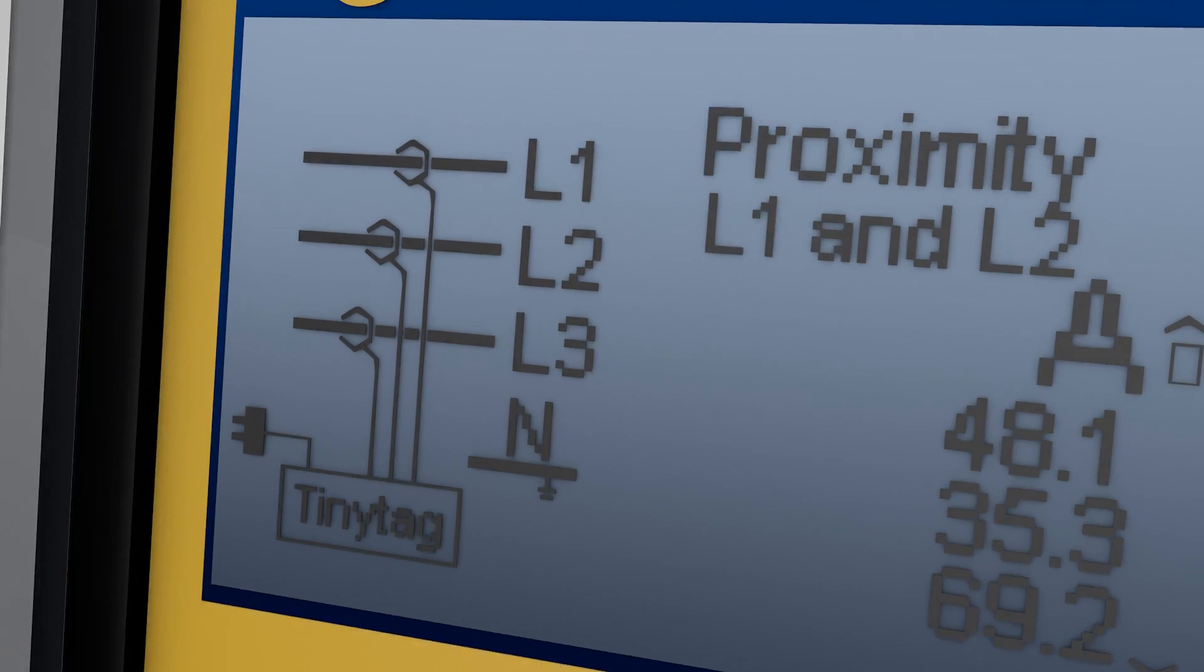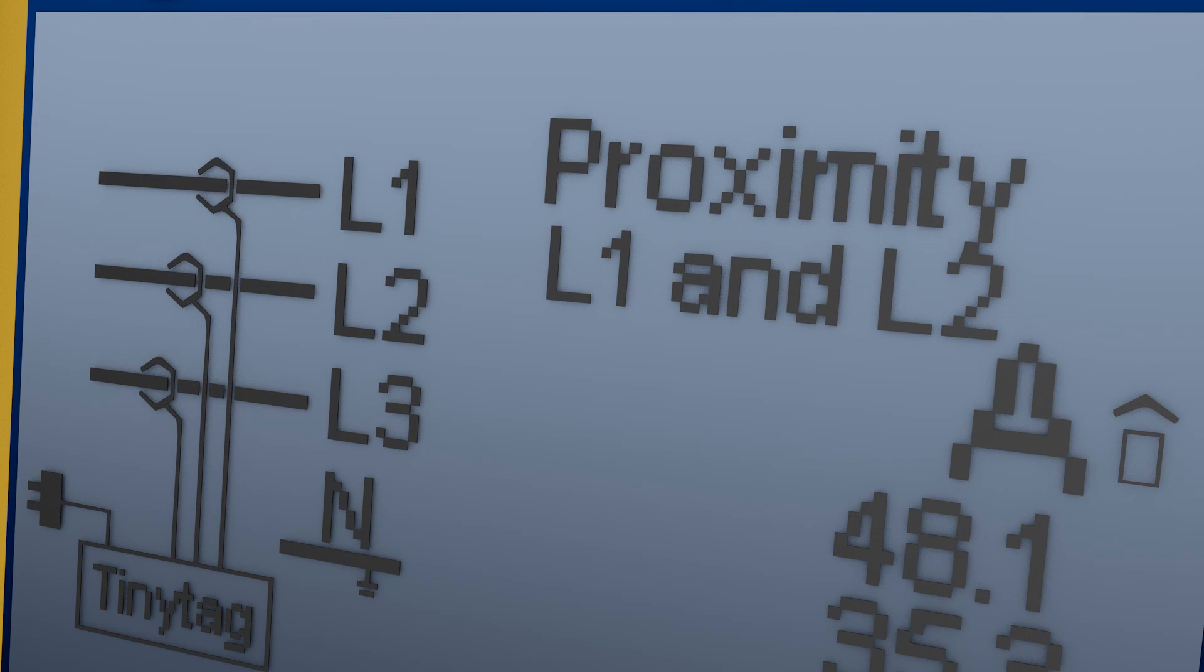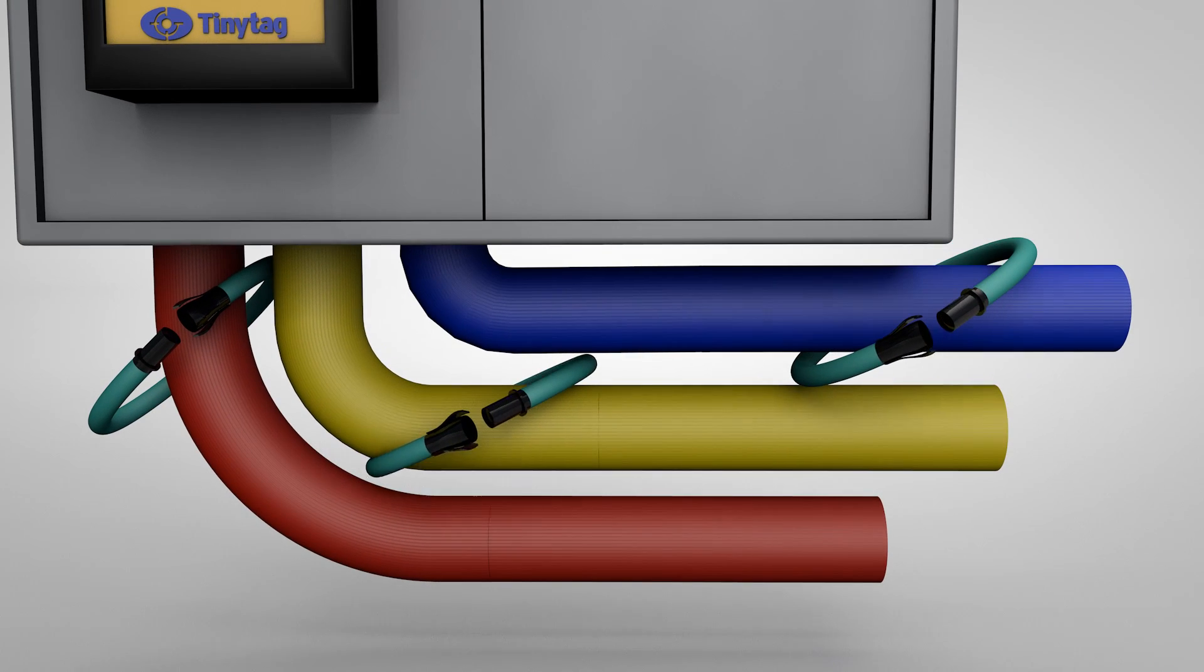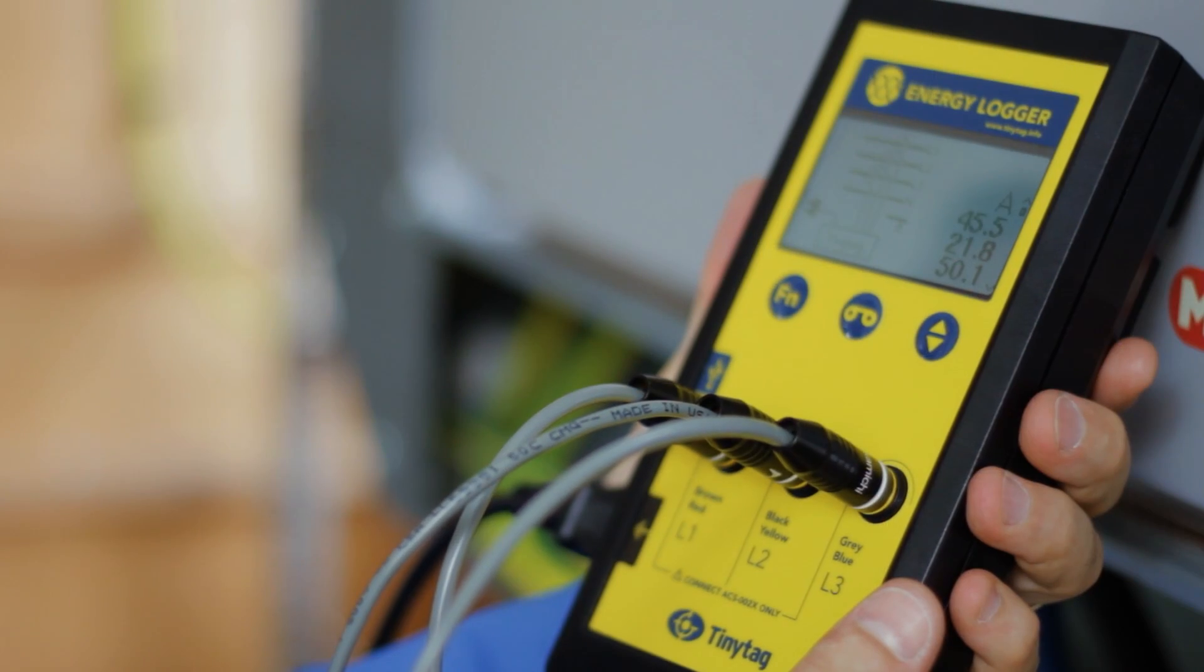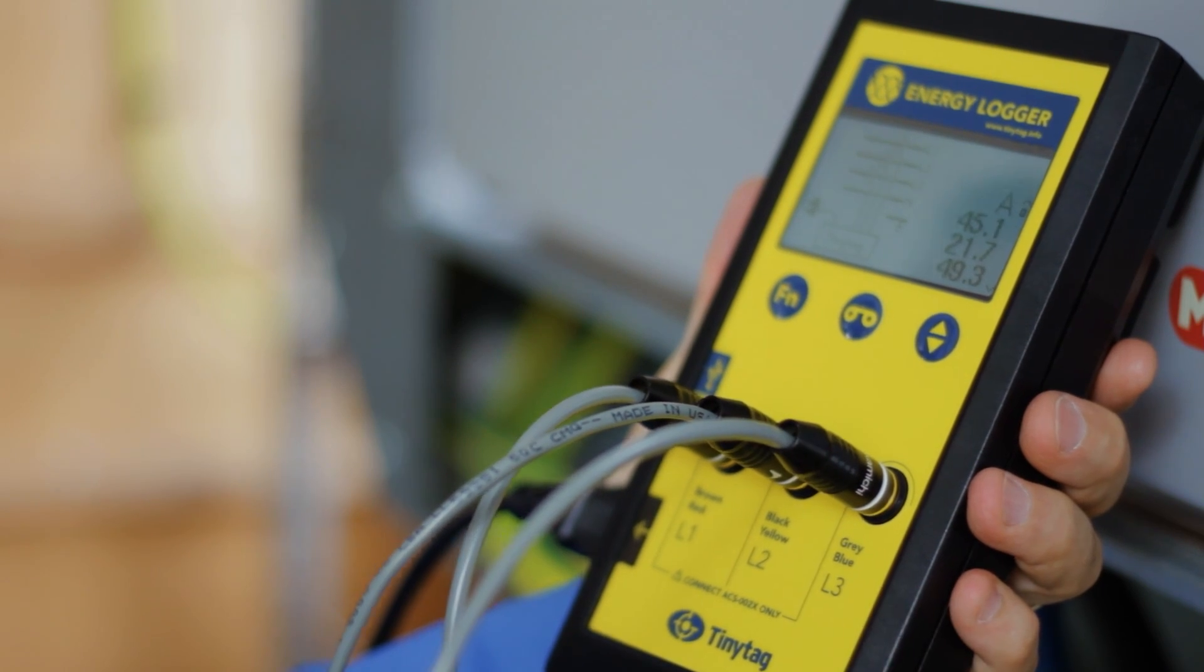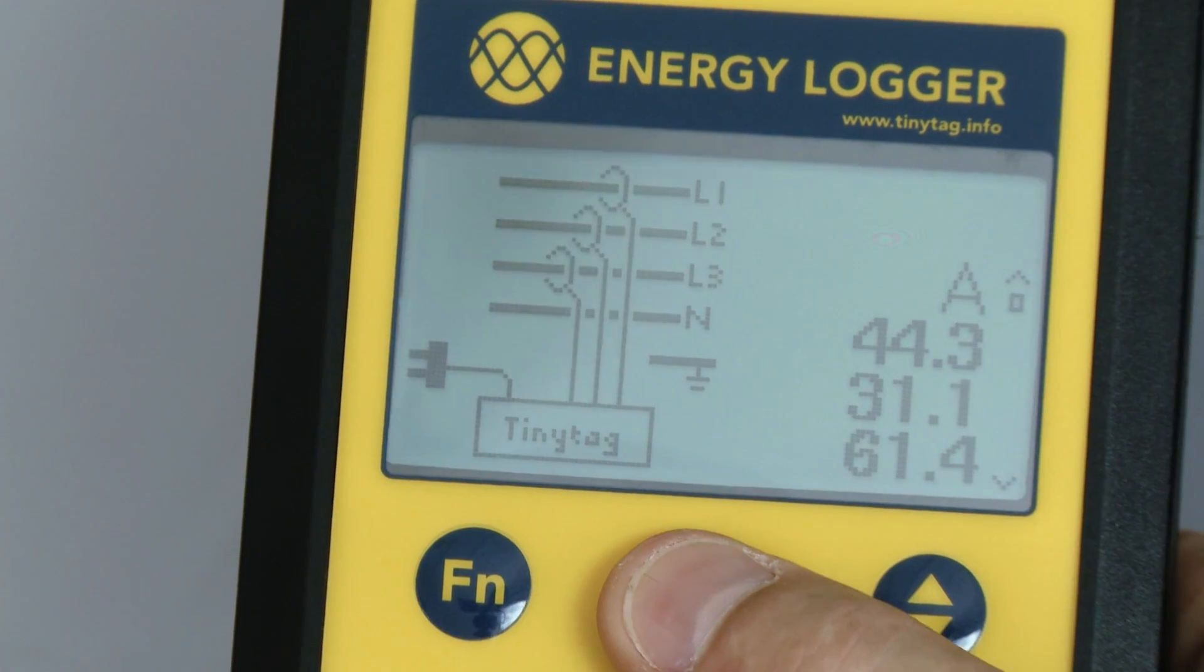Automatic phase detection starts, with on-screen prompts indicating whether the coils need to be adjusted if they have initially been placed too close together. Once the coils are correctly positioned and the messages disappear, press the record button to start the logging run.